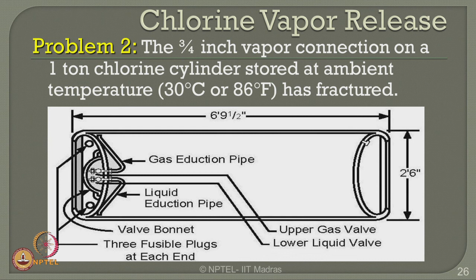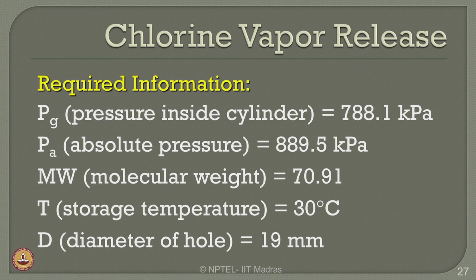Now, a 3/4 inch vapor connection on a given vessel, which is a 1 ton chlorine cylinder stored at ambient temperature, has fractured. The temperature is about 30 degrees Celsius, and the capacity available is 1 ton of chlorine. Let us see what the required information is for solving this problem. Pressure inside the vessel is 788.1 kilopascal, which is given in the problem, which is the gauge pressure. The absolute pressure is of course 889.5 kilopascal. Molecular weight of chlorine is 70.91. The temperature of storage is 30 degrees Celsius, given in the problem. Diameter of the hole is 3/4 inch, which is about 19 millimeter.